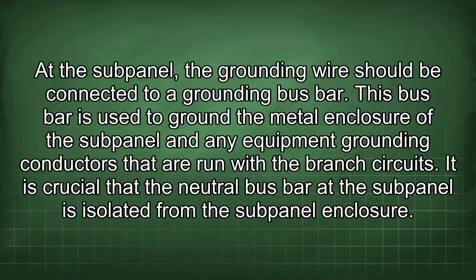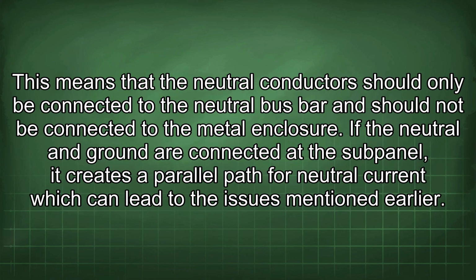It is crucial that the neutral bus bar of the subpanel is isolated from the subpanel enclosure. This means that the neutral conductor should only be connected to the neutral bus bar and should not be connected to the metal enclosure. If the neutral and ground are connected at the subpanel, it creates a parallel path for neutral current, which can lead to the issues mentioned earlier.